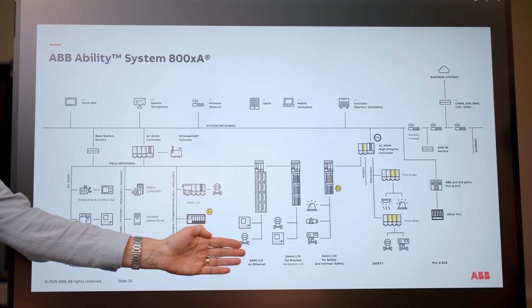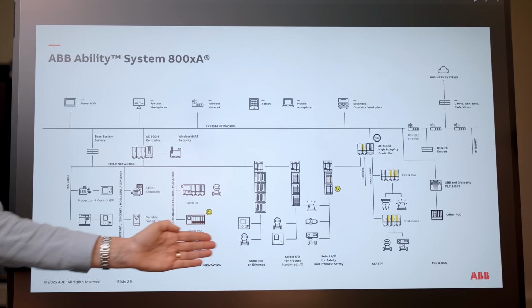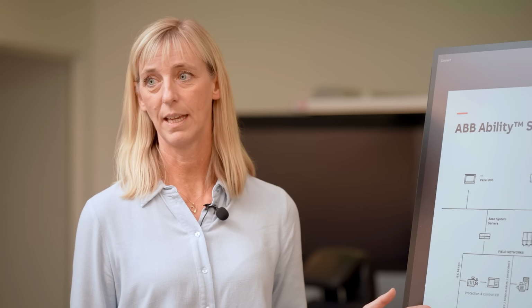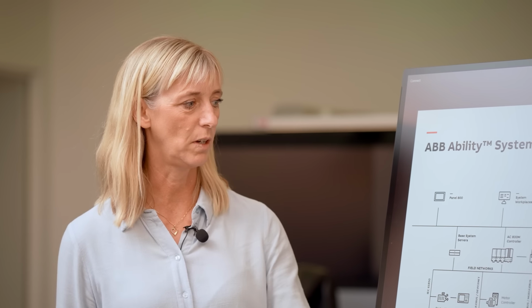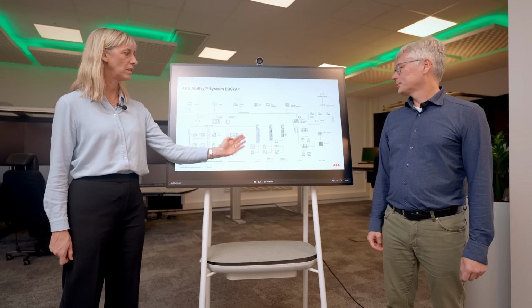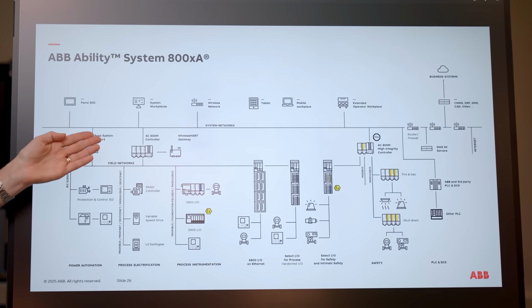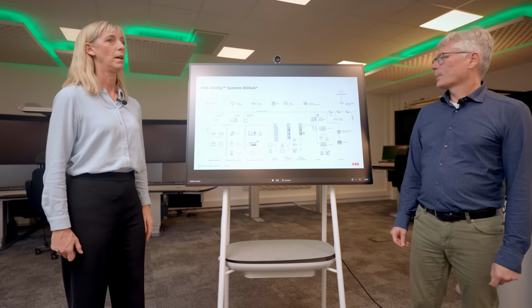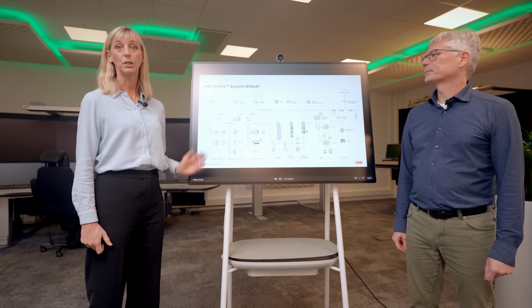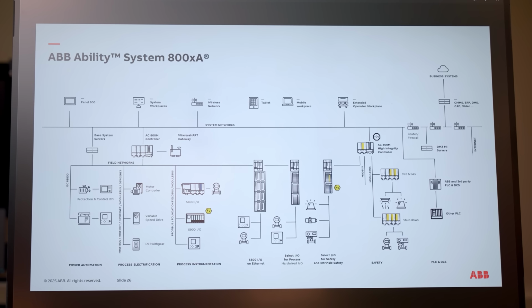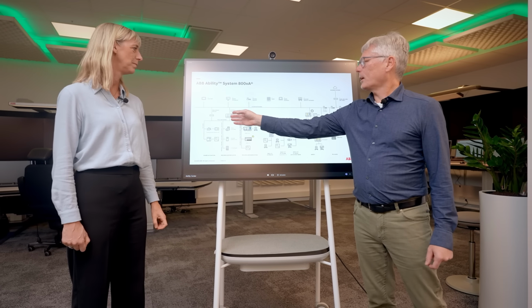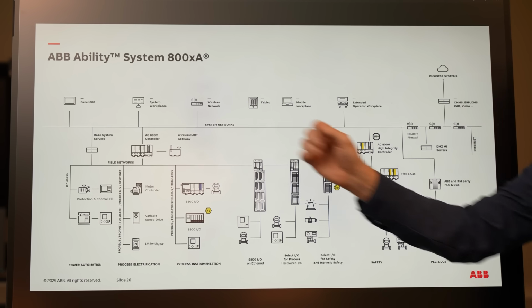Starting from the device level with different devices in the plant, like temperature sensors, level indicators, pumps and valves, etc. And these are all sending and receiving signals from the I/O systems. The I/O systems send and receive those signals to the controller. And in the controller there is a logic loop processing the data sent and received from the I/Os. And from the controllers, the base system servers subscribe to the information from the controllers.